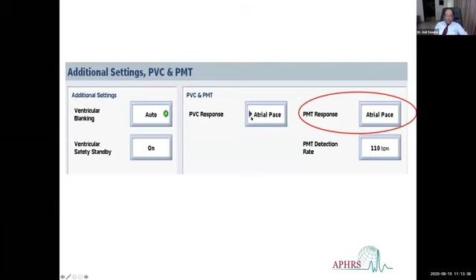There is a PMT response which you can program to whatever you want, A-pace or PVARP extension. And the PVC response also you can program to A-pace or PVARP extension. And that's how it works. So when the patient is having PMT, after a certain number of counted intervals, the pacemaker makes a diagnosis that it's a PMT going on, and instead of giving a ventricular pace on sensing an atrium, it gives an atrial pace, and that restores the normal rhythm. So that's how it can work.